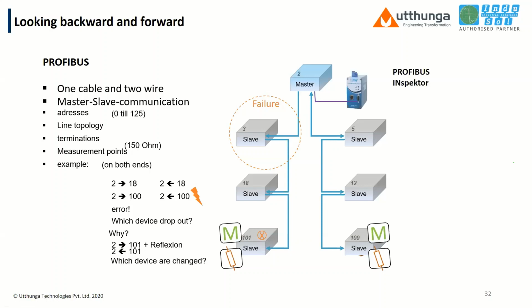permanent monitoring solutions. If we implement a permanent monitoring solution, it will monitor for 24 hours and acquire complete data. It will give correct information, like slave number 3 is having a logical error. Then what do I need to do? I need to test with PBQ1 and pinpoint the error. With the test, I will understand what the exact issue is. I will repeat this. If I connect the Profibus Inspector to the slave, I can understand the specific error in slave number 3, like if it is a logical transmission error, such as an error telegram or repeat telegram, any type of error. Then I will connect PBQ1 in this segment, and I can understand the exact reason for that error by looking at the oscilloscope or the slope of the voltage. I can get into detail.